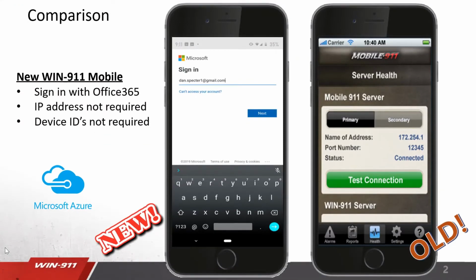First off, let's compare the new WIN-911 mobile app on the left to the old, original Mobile 911. Mobile 911, the original app on the right, required configuration of IP addresses, putting holes in firewalls for both inbound and outbound, and asking users for their IDs in order to set up the configuration. The new mobile app does not require that because we use Azure for our authentication method. Therefore, these device IDs are not required and it's a lot easier to set up.